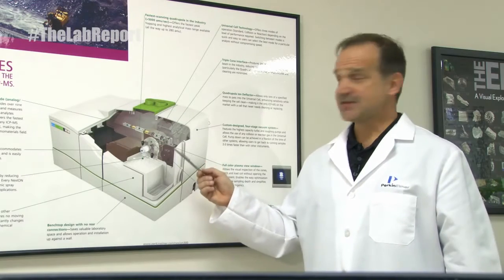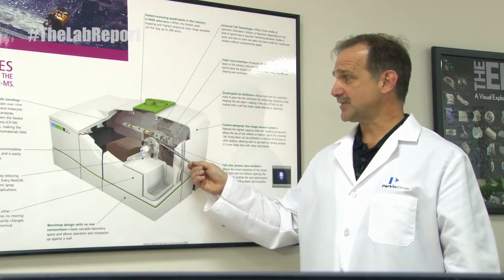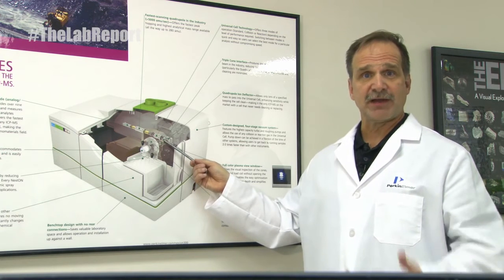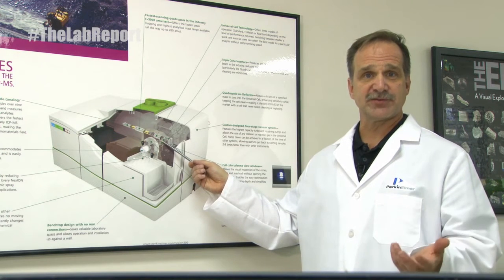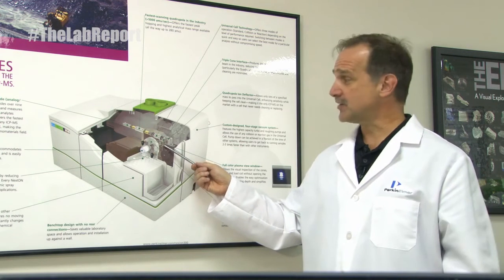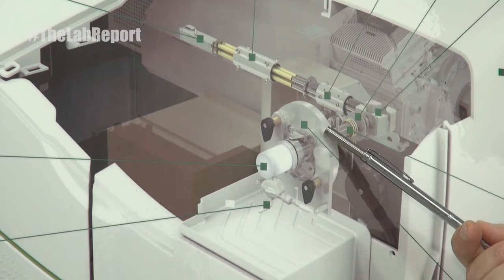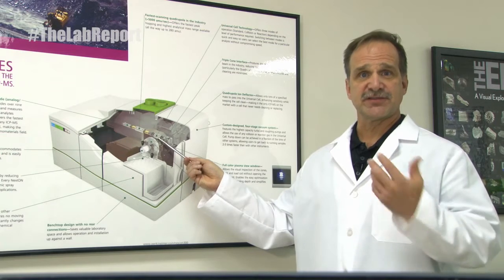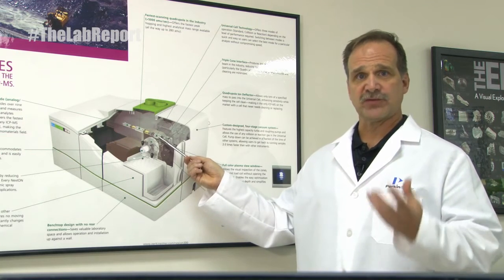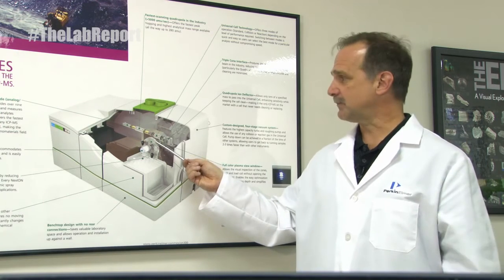After the sample has gone into the plasma, which sits right here, everything's ionized — the elements of interest are ionized — and those ions then pass through the cones. The Nexion uses a series of three cones: a sampler, a skimmer, and a hyperskimmer cone to focus the ions into a beam.